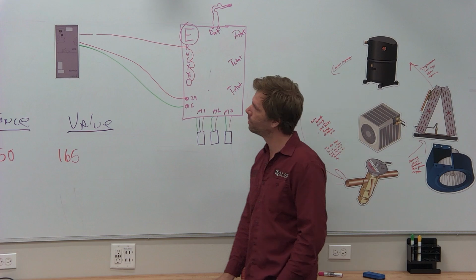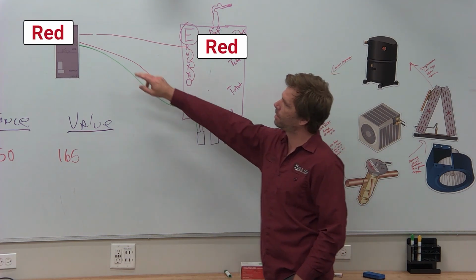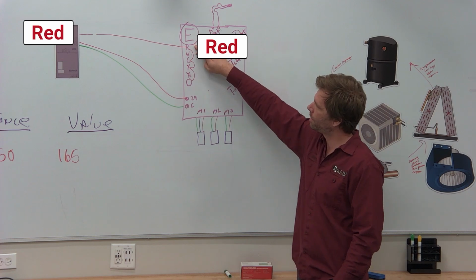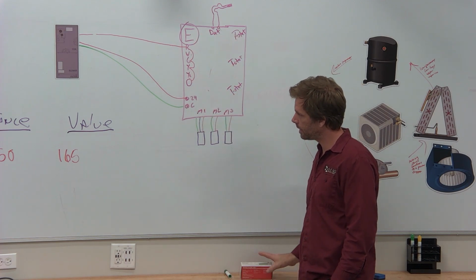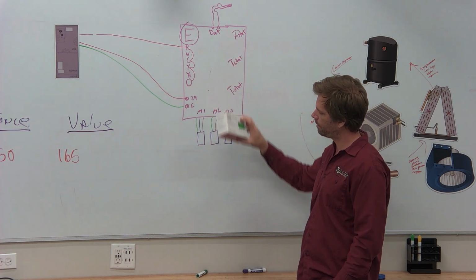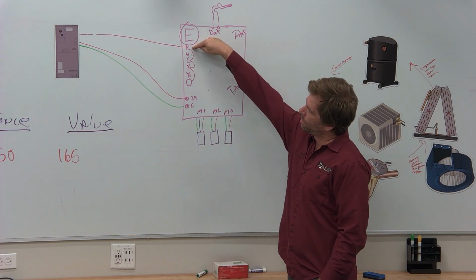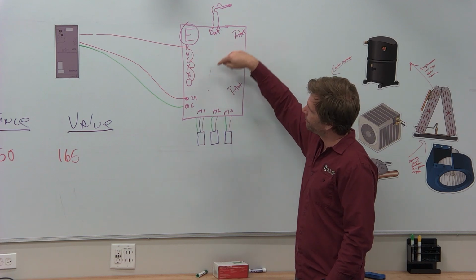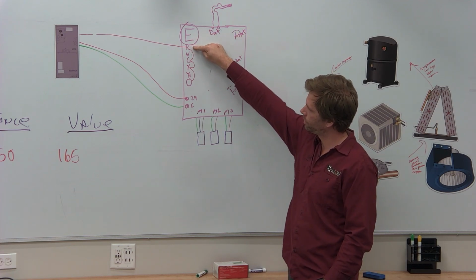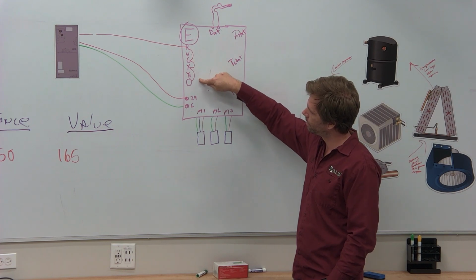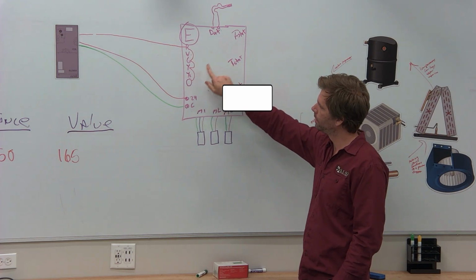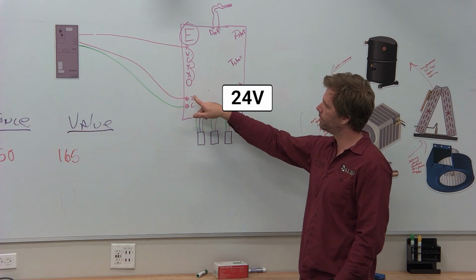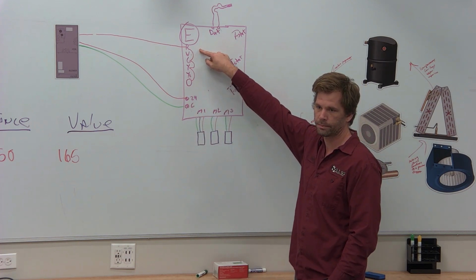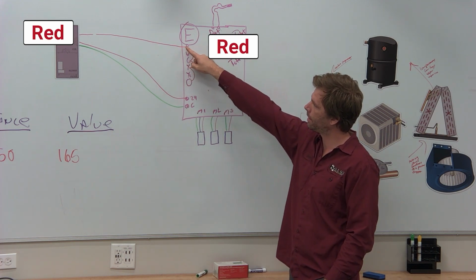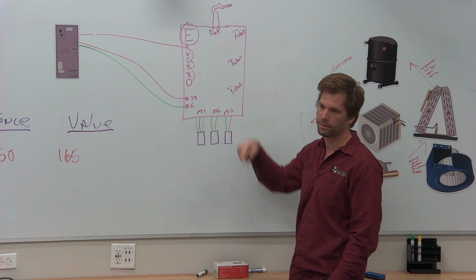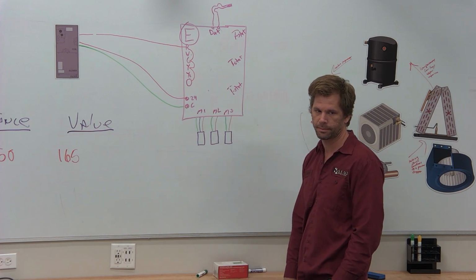So in order to control the equipment, we need the equipment's red coming to our equipment terminal. And then just like with the thermostat, the damper board functions in the same way. When you have your signals to run and everything's in its proper place, red just jumpers to the other terminals in order to call your different modes. Okay? So this 24 volts coming in here is not used to call our equipment. It's the red from our air handler that is used to call each one of these. Does that make sense? Okay, great.